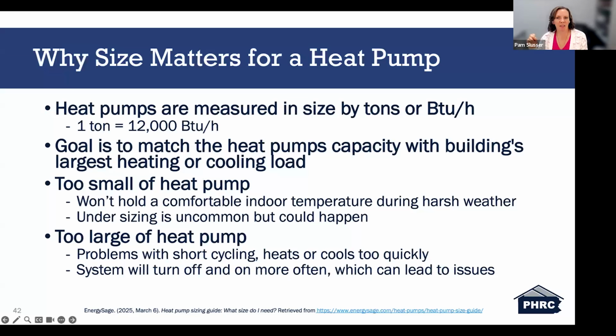So why does size matter for a heat pump? Heat pumps are measured in either tons or BTUs per hour. Just as a reference, 1 ton of heating or cooling capacity equals 12,000 BTUs. So a 3-ton heat pump can deliver about 36,000 BTUs under rated conditions. The goal when sizing a heat pump is to match the system's capacity with the building's largest heating or cooling load. What happens if the system is too small? If it's too small, it may struggle to maintain comfortable indoor temperatures during extreme weather, especially during cold snaps in Pennsylvania. So you want to make sure that it's sized just right.